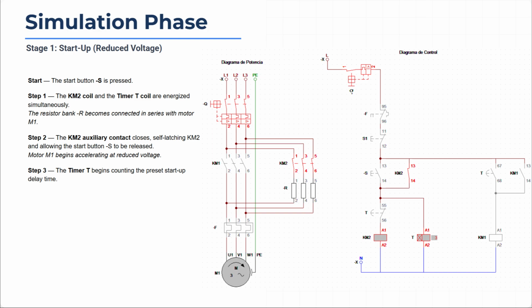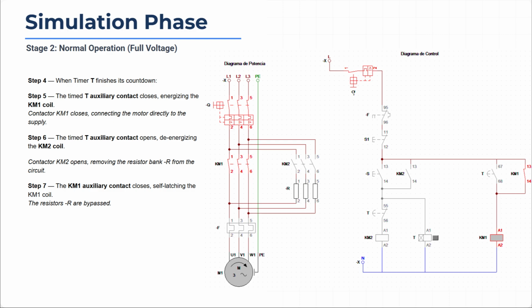Stage 1. Startup. When the start button S is pressed, the KM2 coil and the timer T are energized simultaneously. The resistor bank R connects in series with motor M1. The auxiliary contact of KM2 closes to latch the circuit, and motor M1 begins accelerating under reduced voltage. Stage 2. Normal operation. When the timer T completes its countdown, its auxiliary contact closes, energizing the KM1 coil. KM1 closes, connecting the motor directly to the supply. Simultaneously, the timer auxiliary contact opens the KM2 coil, removing the resistor bank R from the circuit, leaving the motor operating at full voltage.